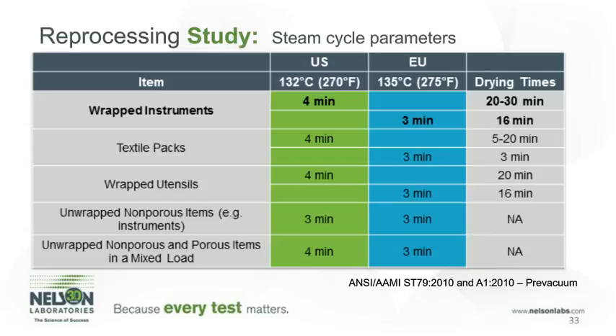In the U.S., the most commonly used cycle is 132 degrees Celsius, and the sterilization exposure time is a 4-minute exposure time. The most common parameters in the EU are 135 degrees Celsius with a 3-minute exposure time. Many of our clients need to validate both of these parameters as they market to both of these areas. We have found that a lot of trays will pass through a combo sterilization cycle of these two parameters, in which we use 132 degrees Celsius and a 1.5-minute half cycle time. Therefore, our clients can test both of those cycles in one sterilization cycle, thus decreasing their time of testing and their expense.